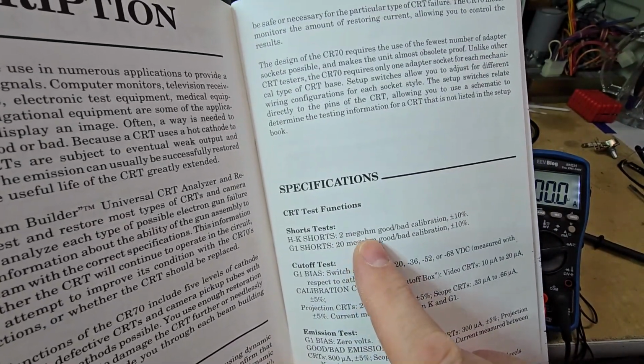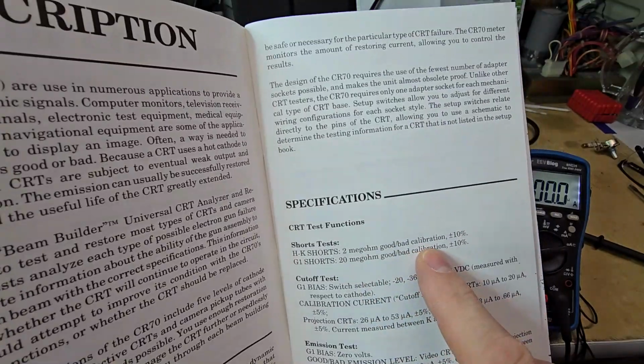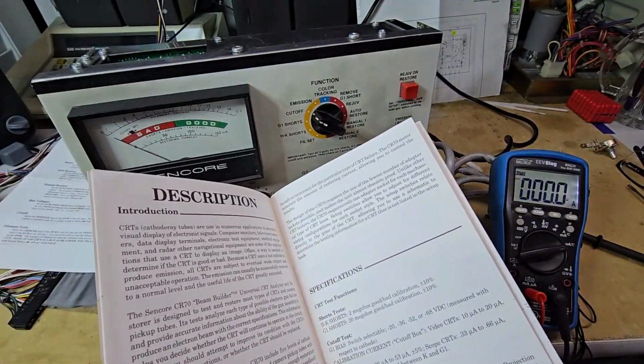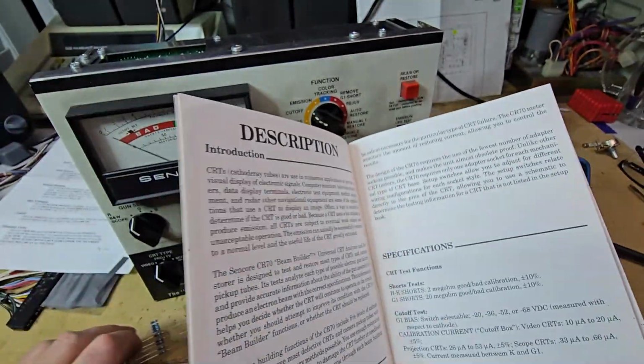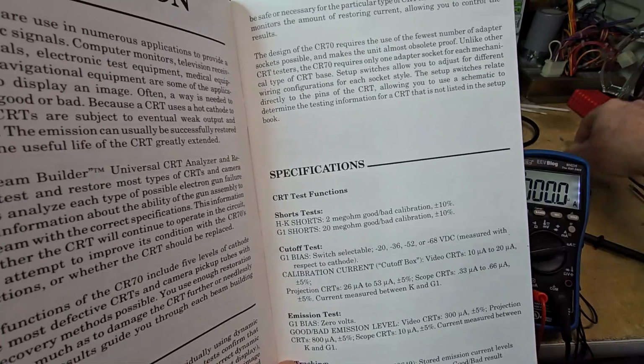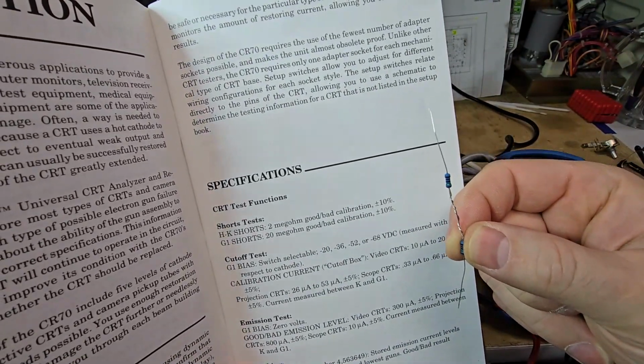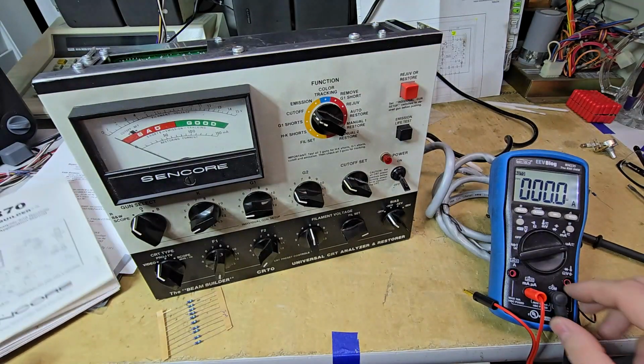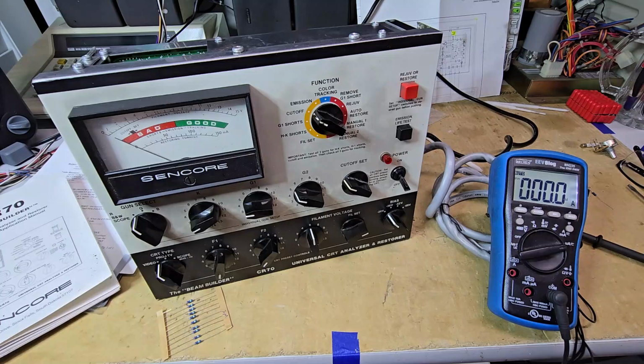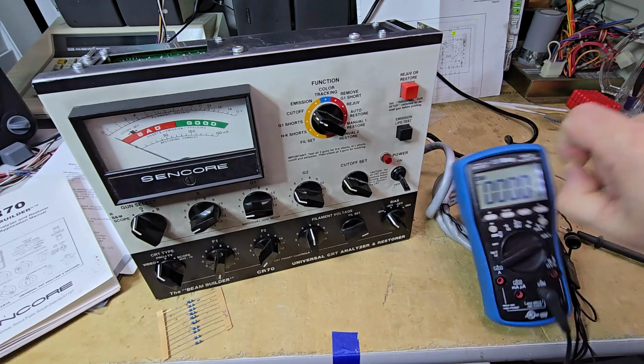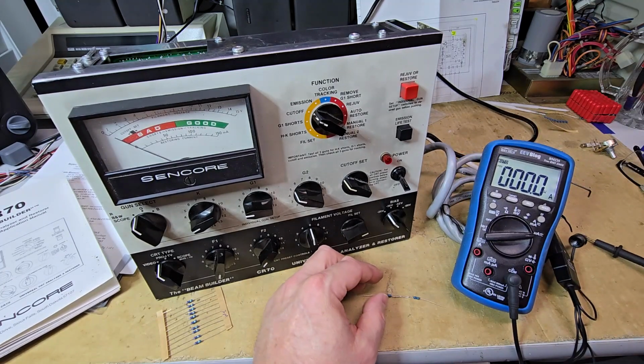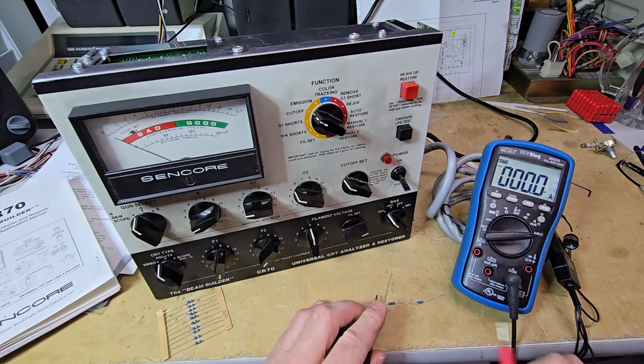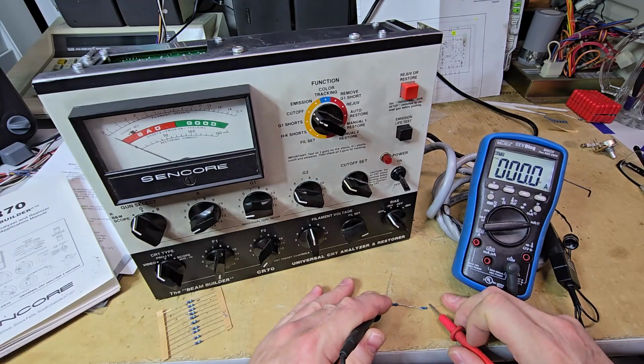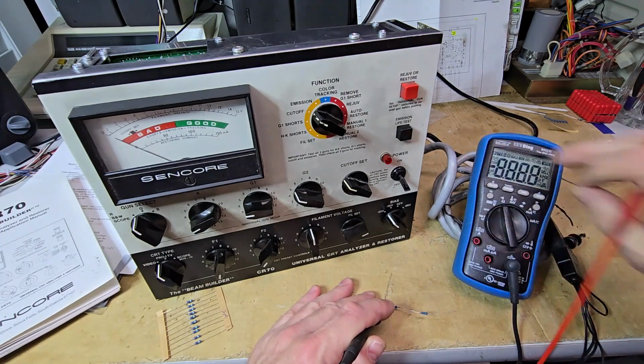All right, next is the shorts calibration, and it says HK shorts 2 mega ohm plus or minus 10%, G1 shorts 20 mega ohm. I have a 2 mega ohm load here, and then I use two 10 mega ohms here, and we'll go ahead and set this up. Basically, what you got to do is, let me get this out. Everything's powered off. This should be 2 mega ohms. If I plug in my thing.